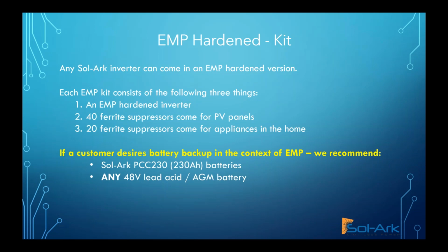When you order one, it comes with three things. The kit comes with the inverter itself, which is EMP hardened, and then it comes with 2 sets of ferrite suppressors. We're going to see those in the next slide. There are 40 of the ferrite suppressors that are for the PV panels, so you can have up to 40 panels in your array, and the 40 ferrite suppressors go on the back of the PV panels. It also comes with 20 ferrite suppressors that are for appliances in the home. Very easy. The ferrite suppressor clamps onto the power cord of the appliance. Again, we'll see that in the next slide. Super easy. So the kit from Sol-Ark for EMP hardening is the inverter and the 2 sets of ferrite suppressors.